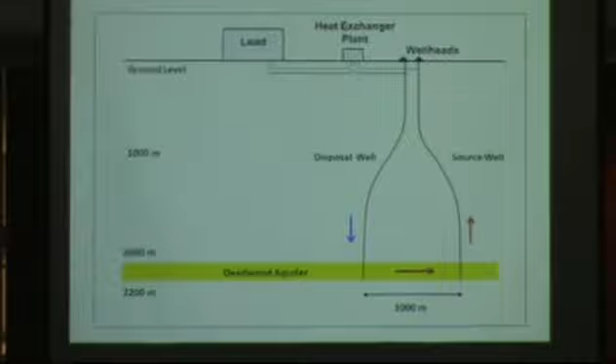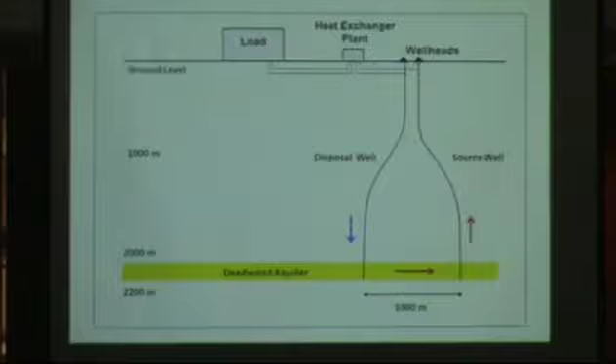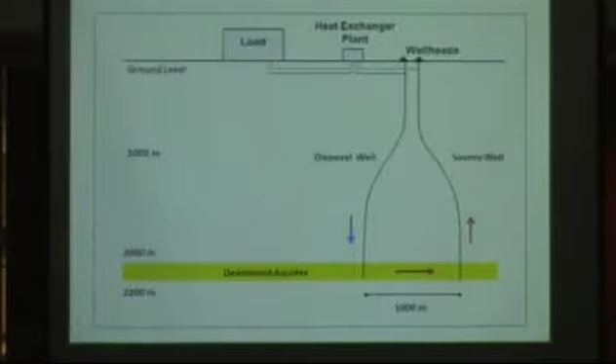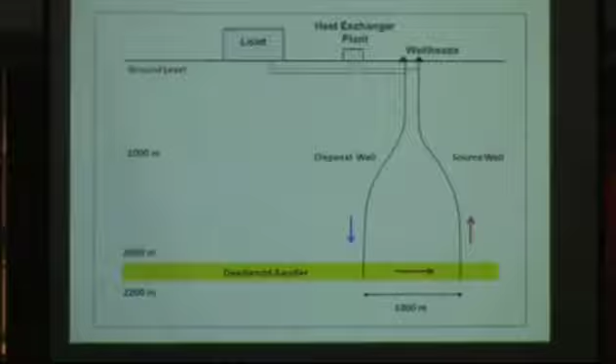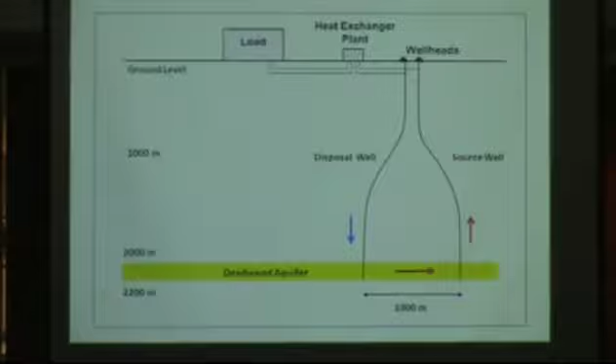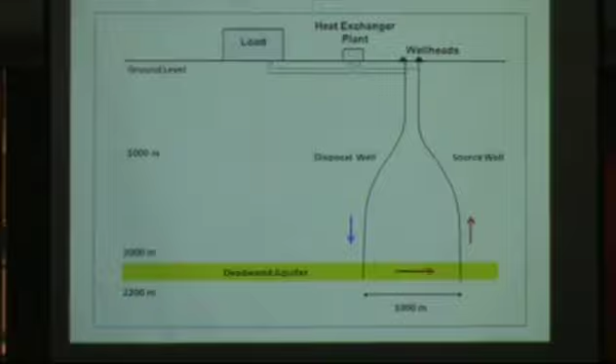So if we look at it operating at capacity for the winter, and then at partial capacity on the shoulder seasons in spring and fall, and it's essentially turned off in the summertime, we've actually doubled the overall capacity, so we've gone up to 50 to 60 years that one of these things would last for a heating source. Now again, that's based on 1,000 meters separation. We can increase that with directional drilling up to 1,500 meters quite easily, or whatever the planned load might be. These things can be adjusted into the overall plan. As is brought forward, we don't want to oversize something necessarily.